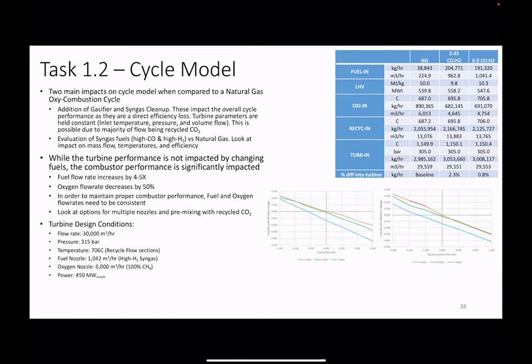One important aspect is that the cycle will most likely be started up with natural gas, so we have to develop a turbine that can be co-fired between natural gas and coal syngas, which changes the combustor design significantly. However, in terms of turbine design, we want to maintain turbine inlet conditions at similar pressures, similar temperatures, but mainly similar volume flow. That's really the three key design parameters of a turbine, so by maintaining volume flow, temperature and pressure we can maintain turbine performance across these different fuels, and we just need to balance the cycle to accommodate that.